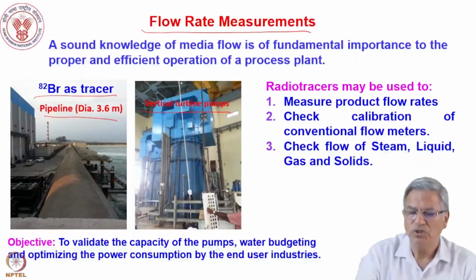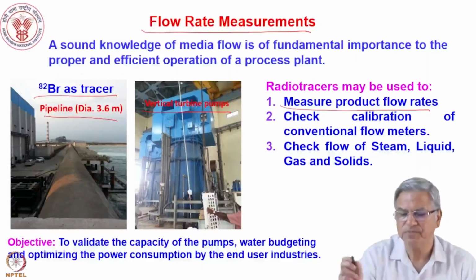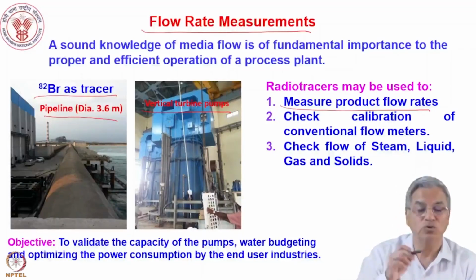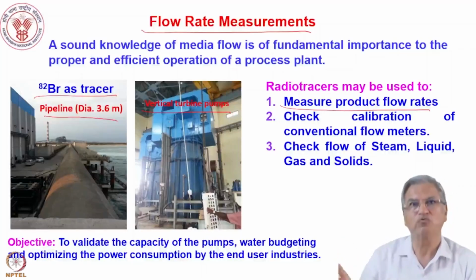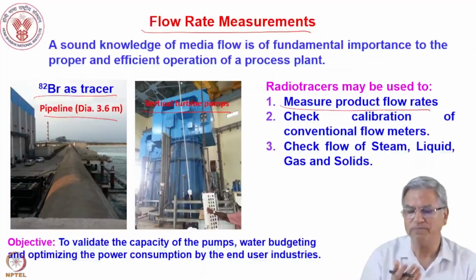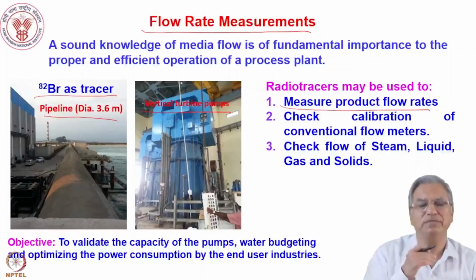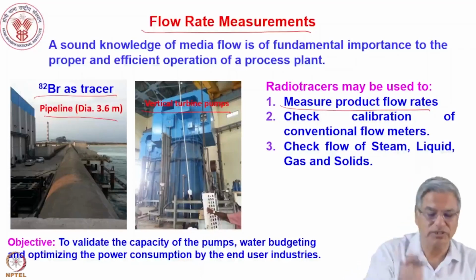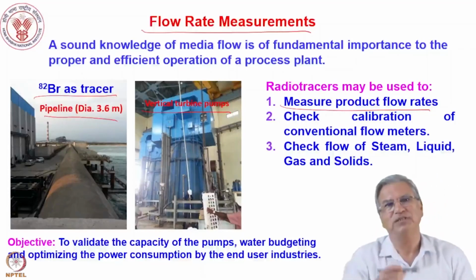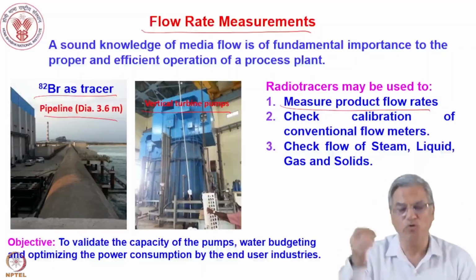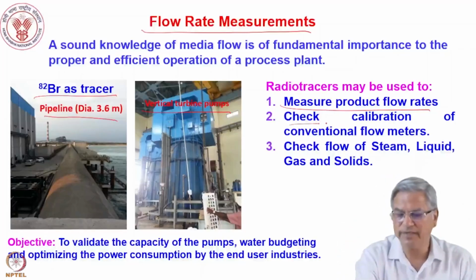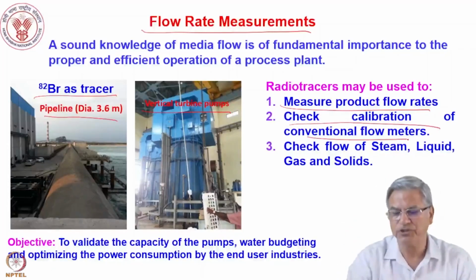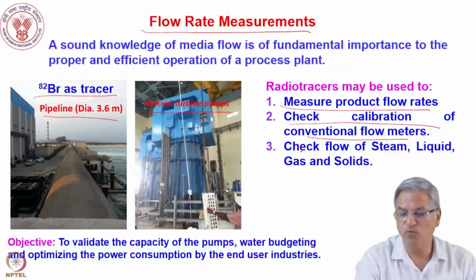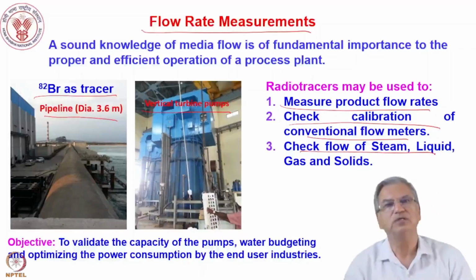To measure the flow rate of water, you can mix sodium bromide into it, and the bromine will flow along with the water. Using this technique, you put suitable detectors at the initial and final stages and observe the activity flowing. This way you can check the calibration of flow meters, or check the flow of any fluid, steam, liquid, or gas.